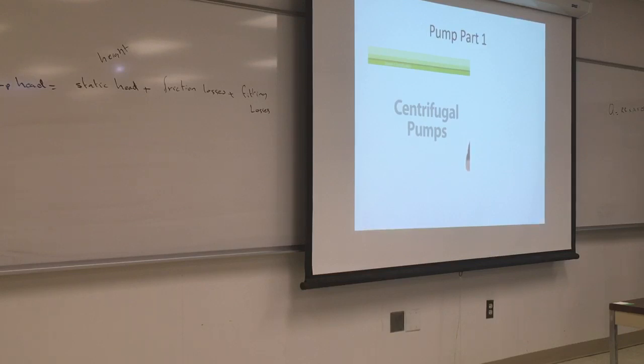Now, before we go any further, let's clear up a very common misunderstanding. We often talk about pumps and circulators as if they're the same thing. Technically, they really aren't. The circulator doesn't lift water the way a well pump lifts water. It circulates water through a continuous loop system by creating a pressure differential. Water enters the circulator at a lower pressure. The circulator then accelerates the water and sends it back out at a higher pressure.